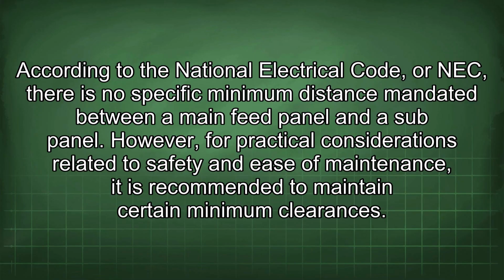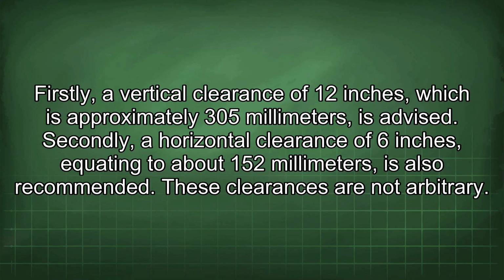According to the National Electrical Code, or NEC, there is no specific minimum distance mandated between a main feed panel and a sub-panel. However, for practical considerations related to safety and ease of maintenance, it is recommended to maintain certain minimum clearances. Firstly, a vertical clearance of 12 inches, which is approximately 305 mm, is advised. Secondly, a horizontal clearance of 6 inches, equating to about 152 mm, is also recommended.